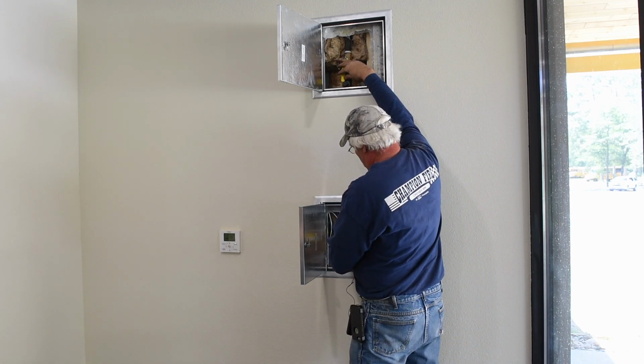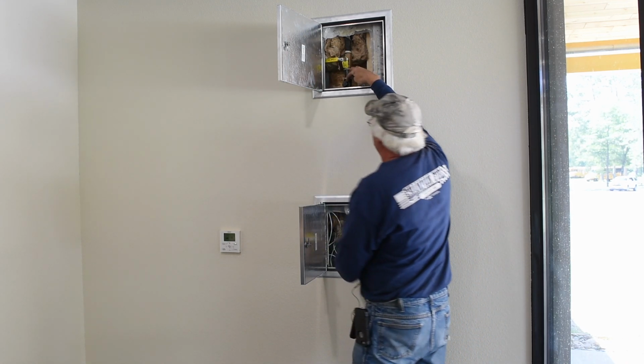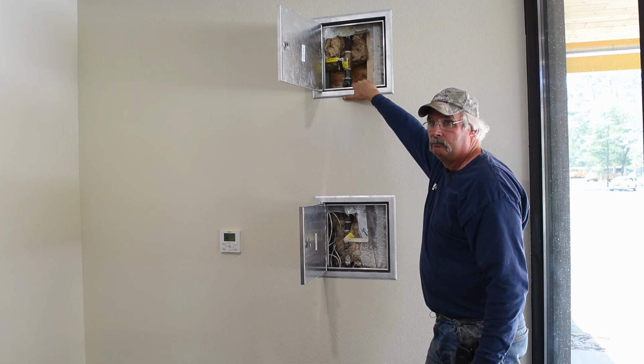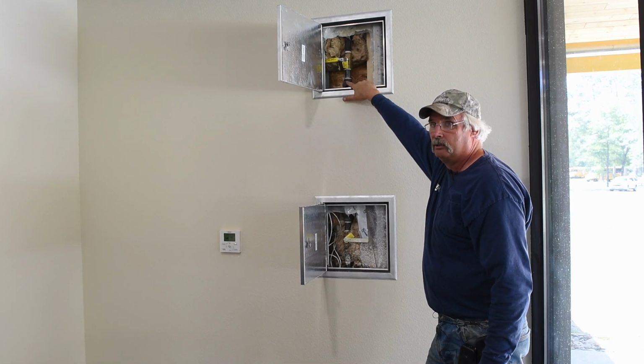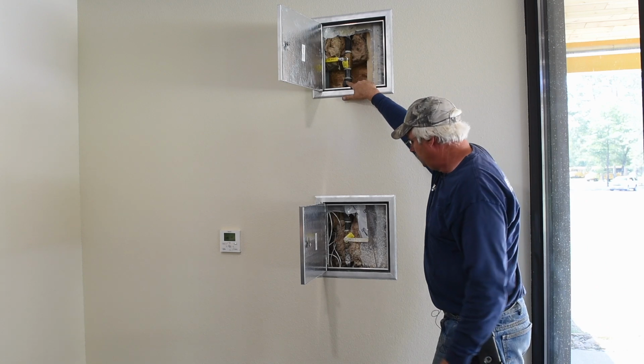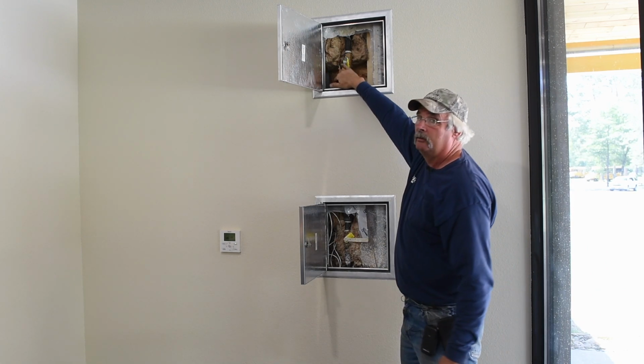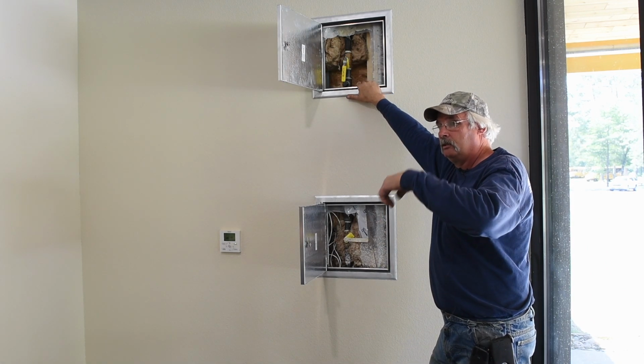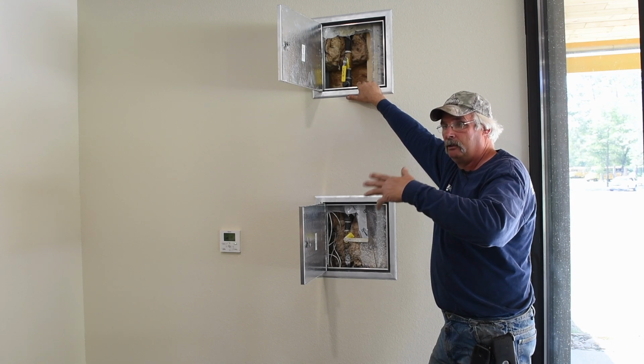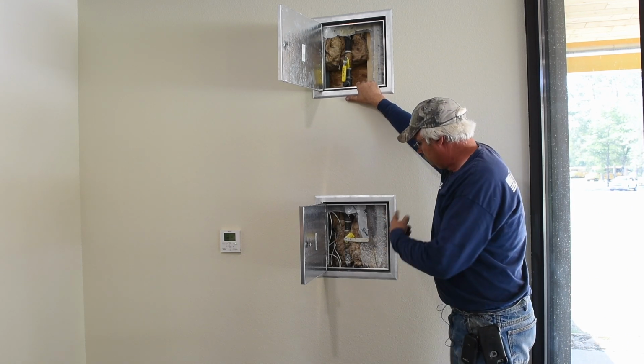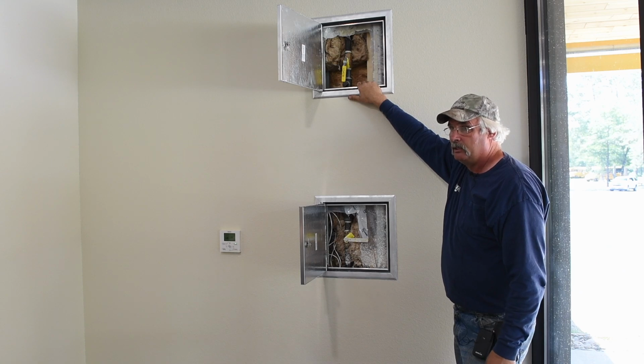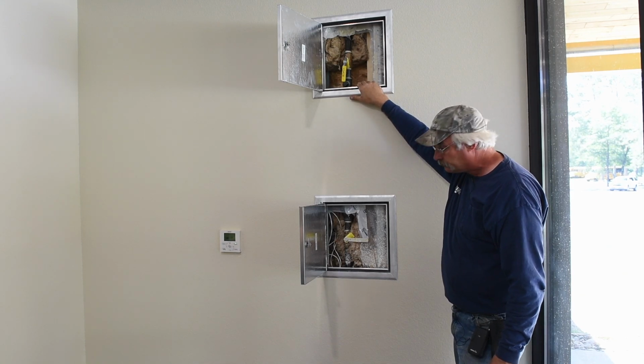When I get done, I shut both valves, pull this plug, put glycol in, like a pint of glycol, put the plug back in, dope and tape it back up. Leave the top valve open. That way, if any moisture gets in there, it'll mix with that glycol and it won't freeze. And down and out.